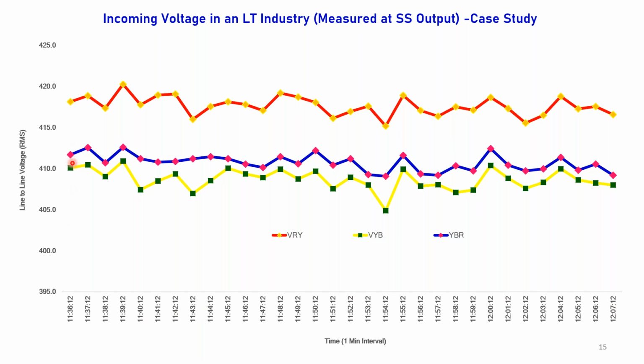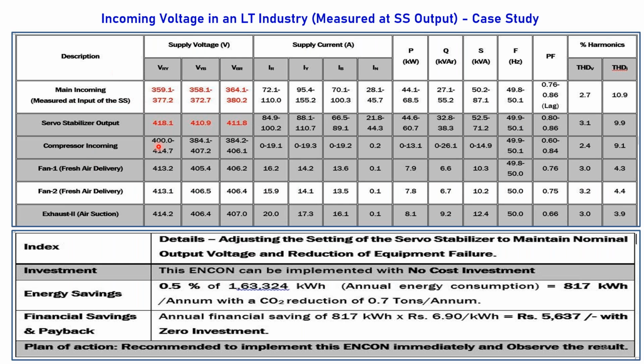Now the line voltages of all the phases are not equal, and this is reflected throughout the entire day. R phase has a higher voltage compared to the Y phase and B phase. Initially we thought the input side would be very high, so at the load side it may be lower. But when we took the readings at each and every point, we found that the R phase voltage is still higher than the Y phase and B phase voltage.